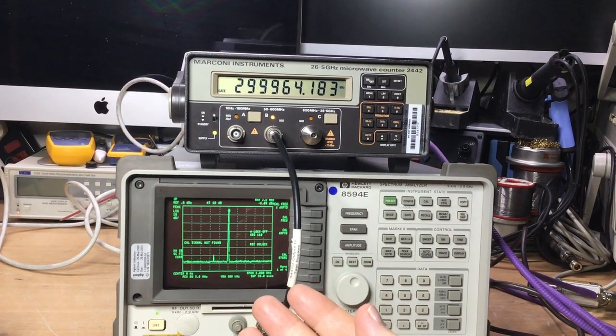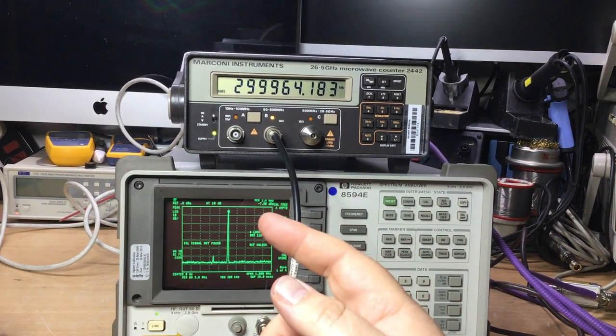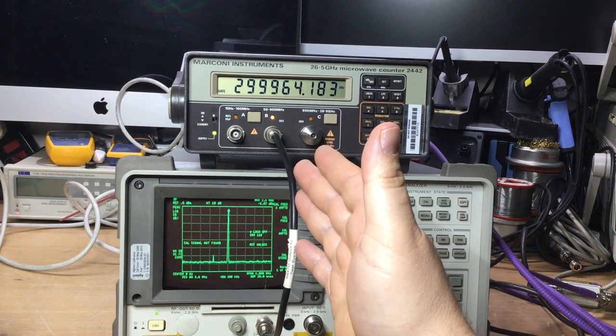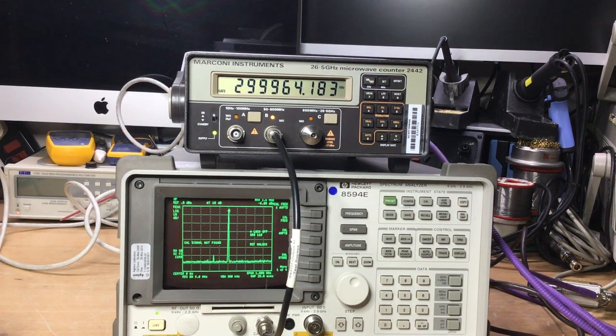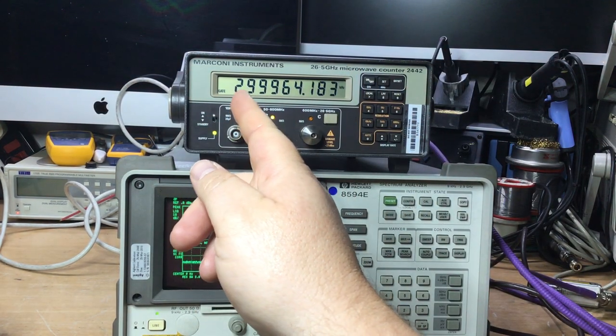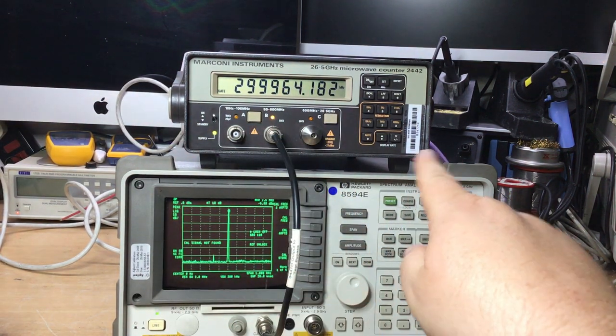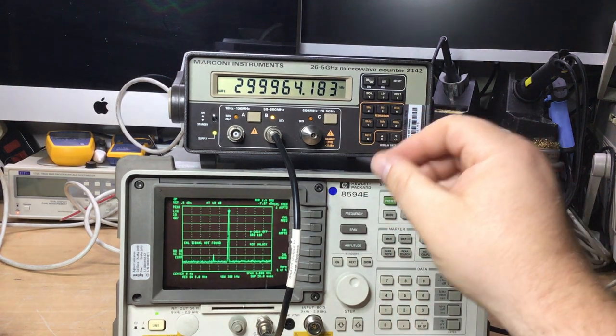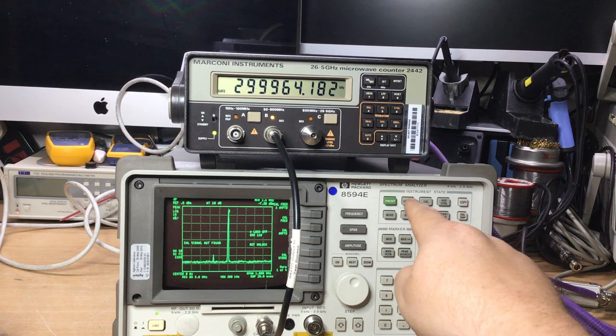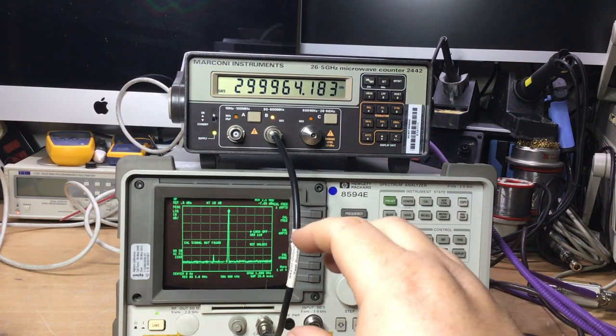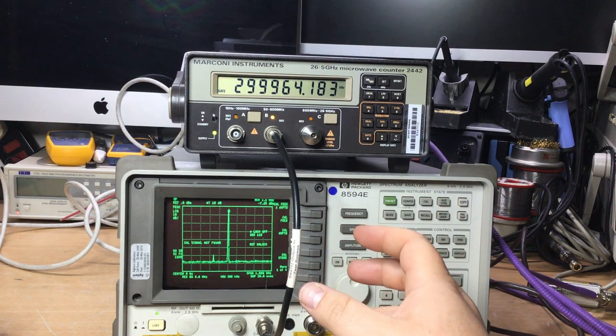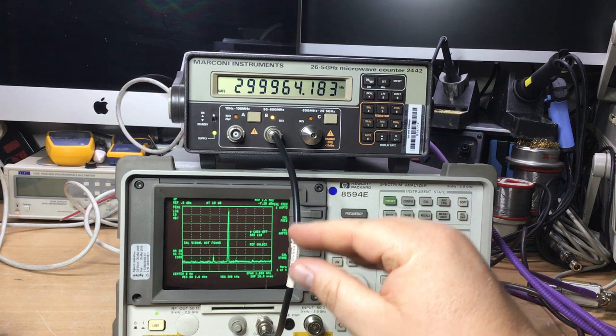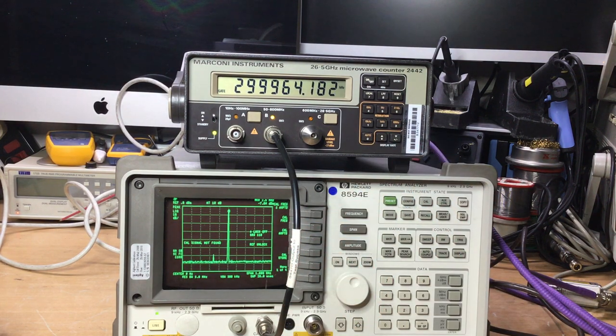Now we're going to measure the level shortly using another Marconi instrument, separate, with a power probe. So we'll look at the level coming out, but first of all we'll just concentrate on the frequency. Obviously if the frequency is off, which it is here, it's reading not 300 megahertz, it's slightly off frequency. It looks around about 30 something kilohertz off frequency there. But inside the spectrum analyzer there's an adjustment pot, and then there's a fine adjustment electronically through the calibrate menu with a DAC setting, so you can change the digital to analog conversion DAC levels, so that basically it will fine tune the frequency of the standard, or alternatively you can just adjust it in the crystal oven, which is within the spectrum analyzer, which when we get the lid off we'll see that.